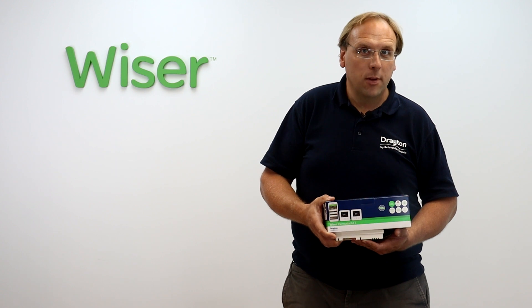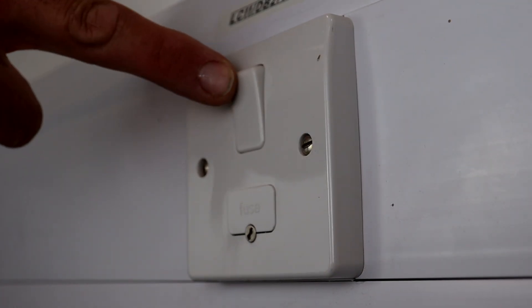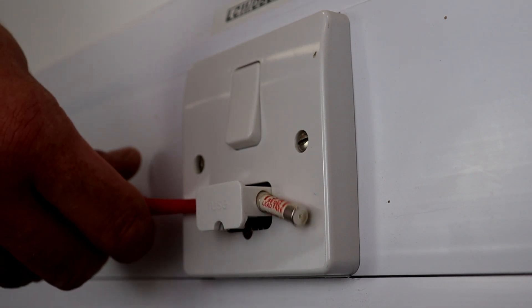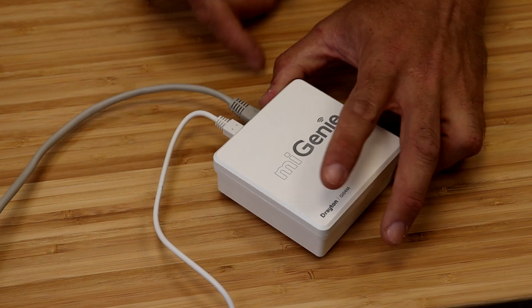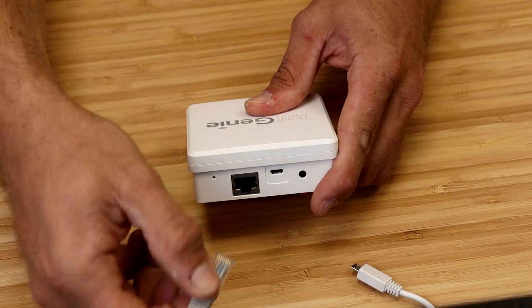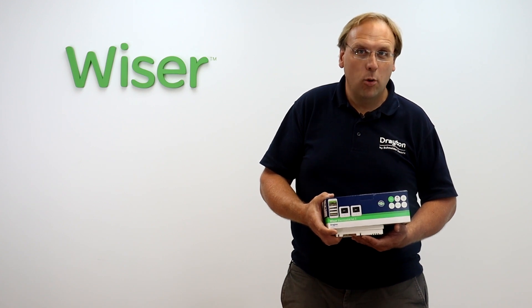Once both of these checks have been done you're ready to upgrade. Begin by isolating the power to your heating system and confirm that the miGenie controller de-energises. Remove the batteries from the miGenie thermostat and power down and disconnect the gateway at your router. None of this equipment is required anymore and the Wiser system will connect to the internet using Wi-Fi rather than a cable. That's the old system decommissioned — you're now ready to start installing Wiser.